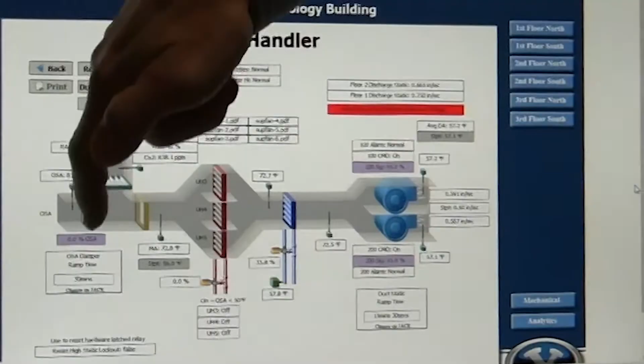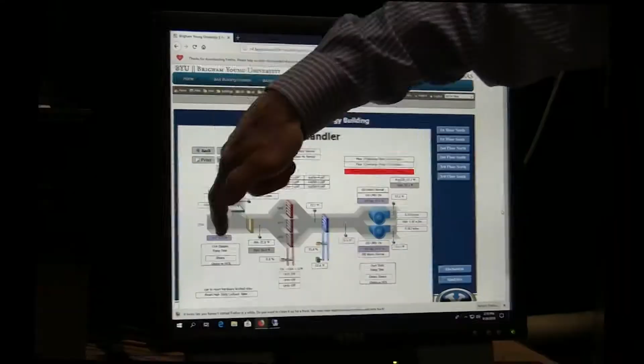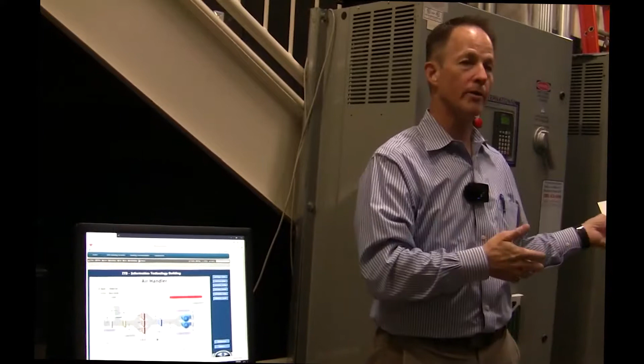But as we've got it right now, our return air dampers are 100% open and the outside air is closed. This is also a good time to verify that your damper's fully closed for outside air as we go into winter, so we don't have any leakage of cold air in the wintertime.